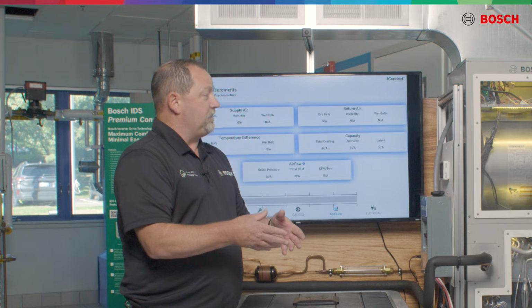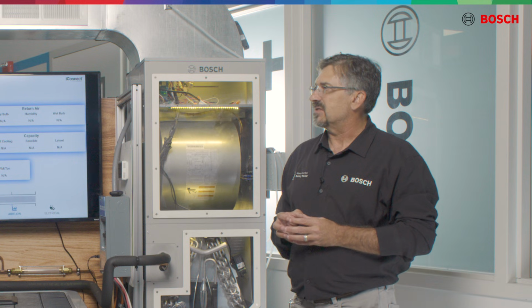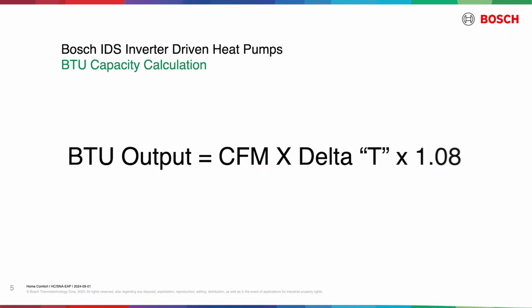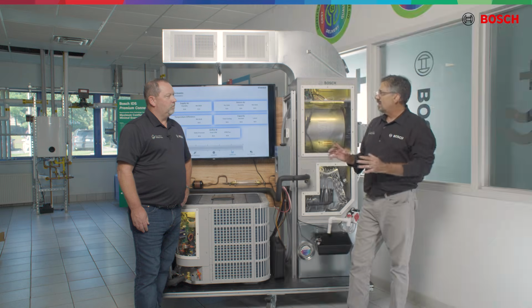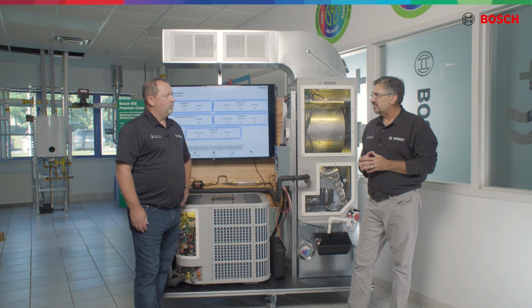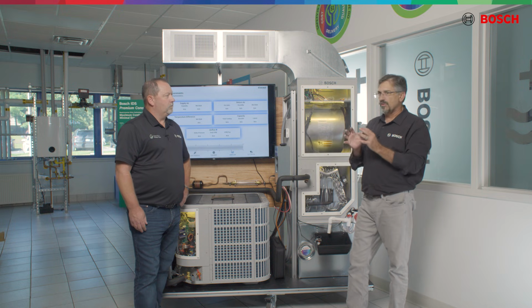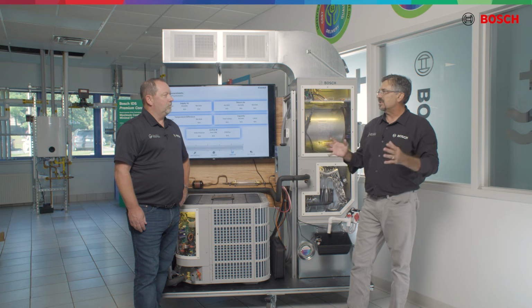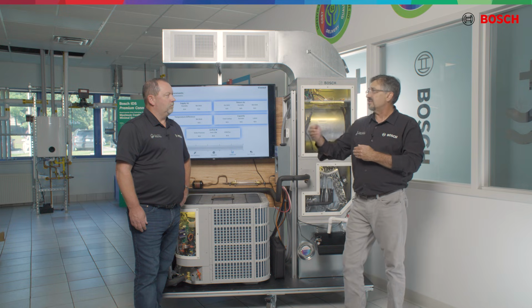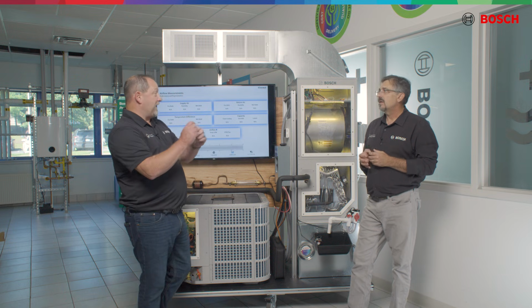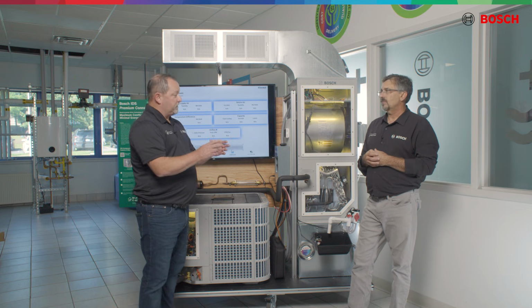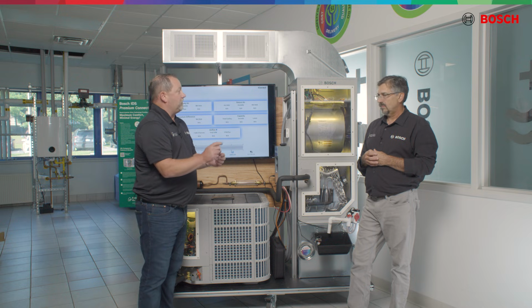We need static pressure. And once we have these, we can put them in a formula and do the math, right? That's right. This is going to give me BTU capacity. We're going to do a BTU output calculation. We're simply going to use a constant of 1.08. That's our air constant. We're going to use delta T, the difference between return and supply temperature. That can prove our coil is working correctly. And the most important thing, Chris, is we need the CFM. We can't guess. This is a 3-ton unit. You just can't guess it's 1,050 CFM because I told you that. You have to prove with your tools that this system in your duct system is in fact providing 1,050 CFM. And the blower chart will help us get that. If we have that static pressure number, in a lab setting it's going to give me that CFM number or thereabouts, right? That's correct.